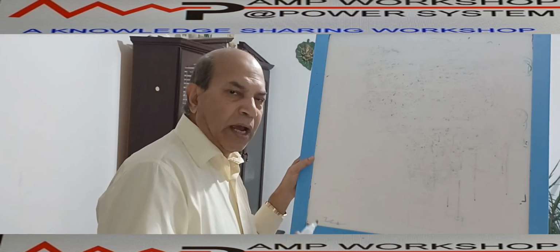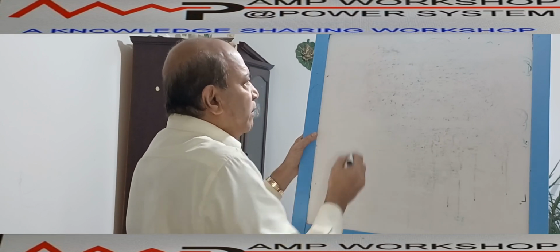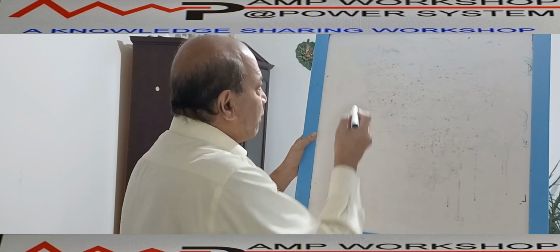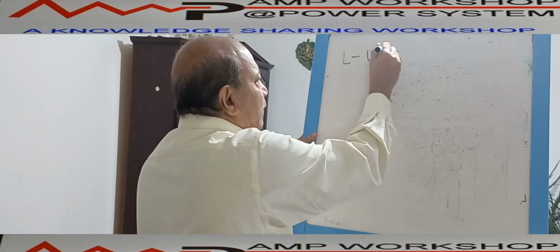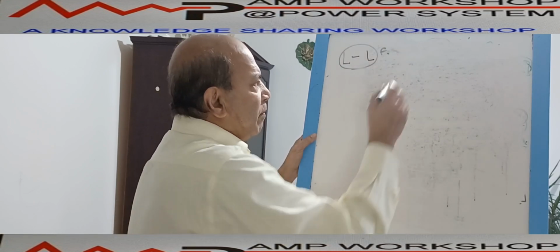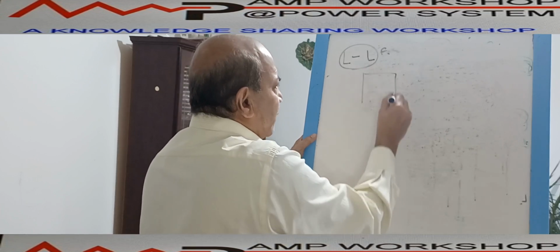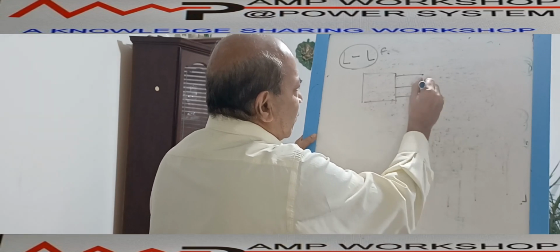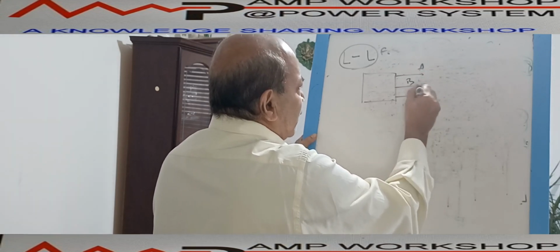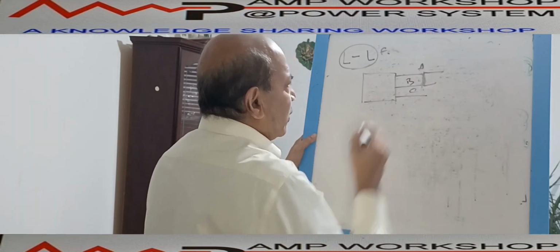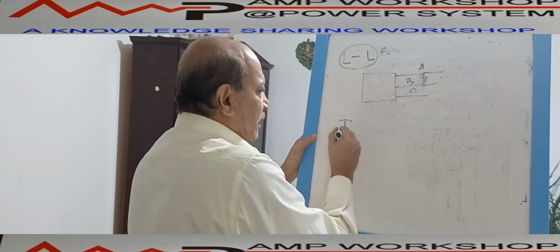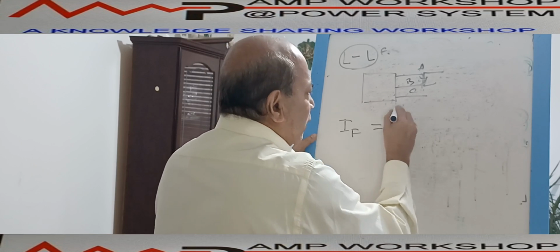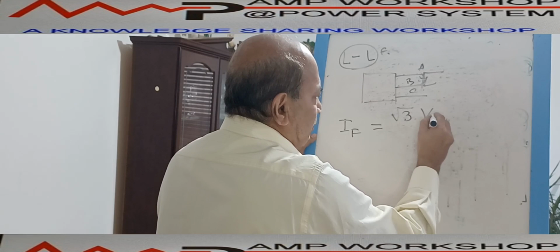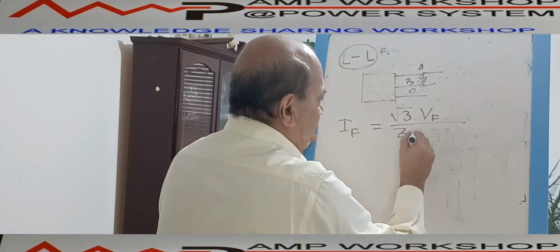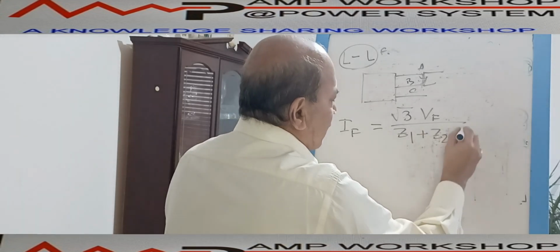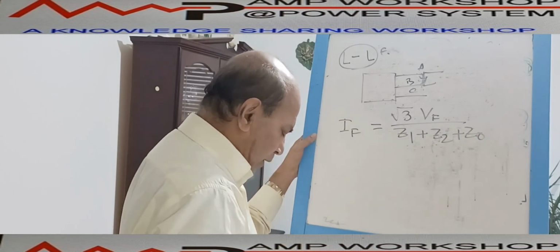In case of line to line fault, if you want to calculate the fault current, it is not the earth fault, it is a phase fault. Line to line fault means between two phase fault. Suppose this is a network, this is A phase, this is B phase, this is C phase. There is a fault over here between these two. In that case, whatever the fault current flowing through this, IF, that equals to root 3 of the fault voltage VF, divided by positive sequence impedance plus negative sequence impedance plus zero sequence impedance. That will be the expression for this fault.